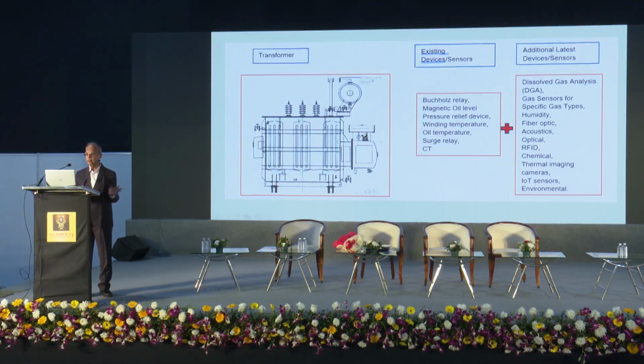So this DGA could be online also, offline also. You can get this through AI. There will be sensors for gas selection. At the nascent stage, you can find out whether it is methane going up, whether it is a hydrocarbon coming up, and you can analyze the transformer at a basic level to determine what type of fault is there.